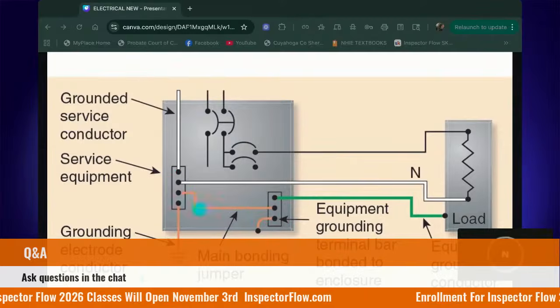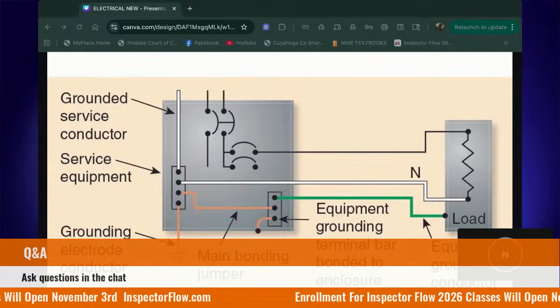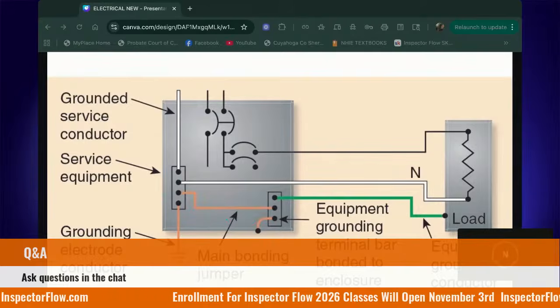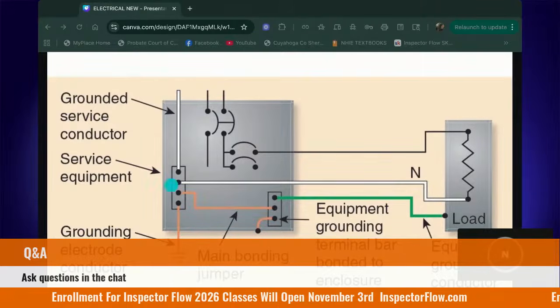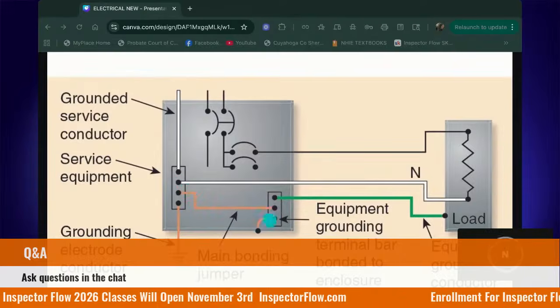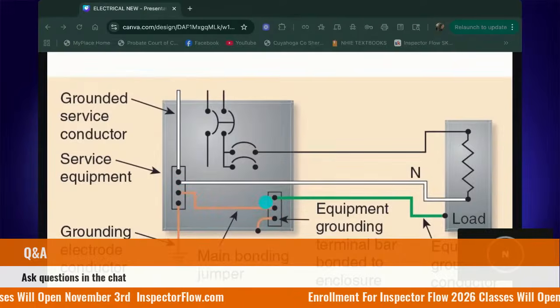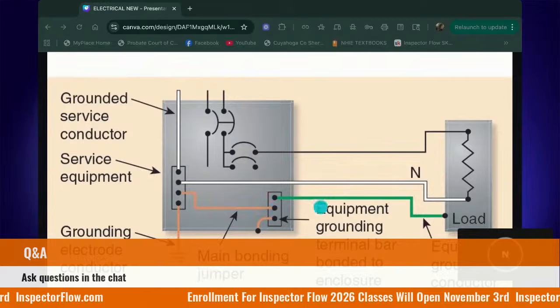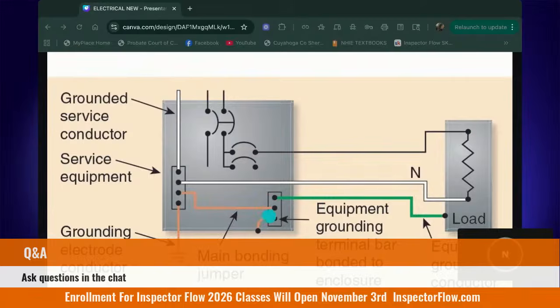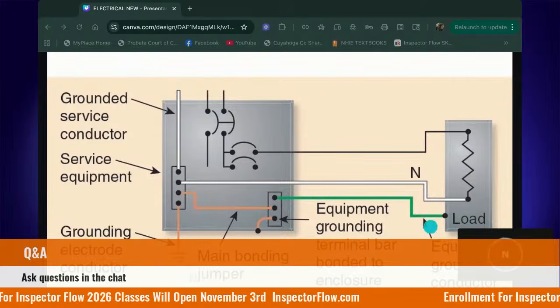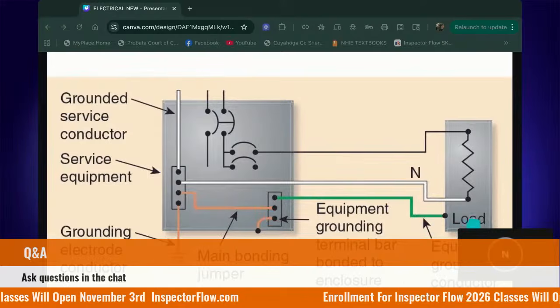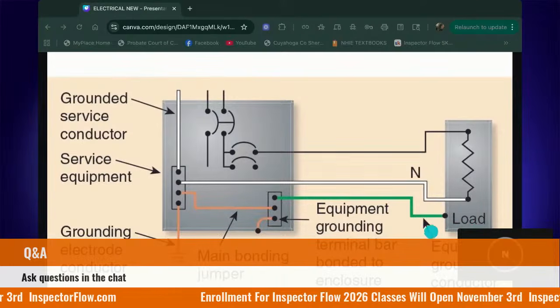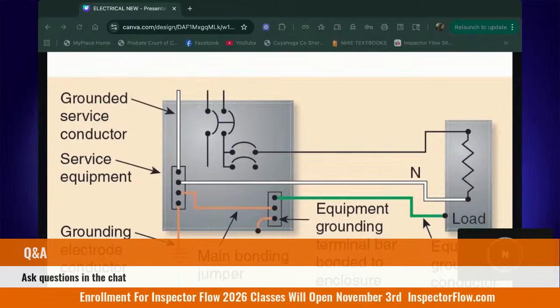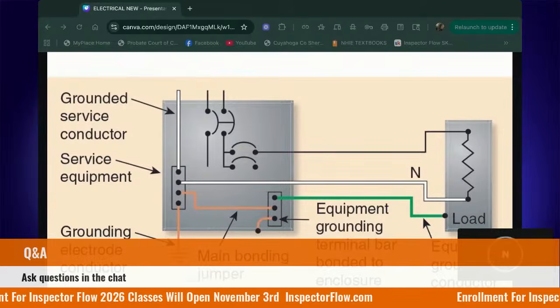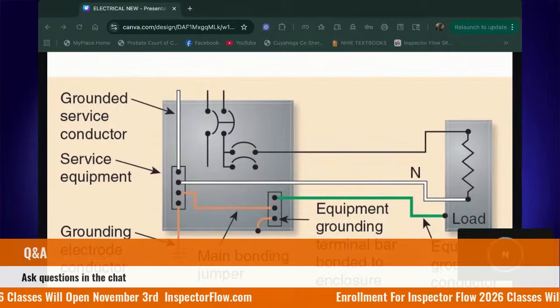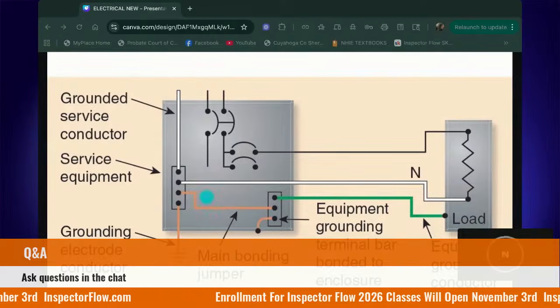It's sort of like we're shaking hands here between the neutral and the ground so they can work together. Then I have my equipment grounding bar, or my grounding bar inside of my panel where my EGCs terminate. So all of my equipment grounding conductors, or EGCs, from my outlets, from my switches and appliances, connect here. They come back to the grounding bus bar. Are these wires carrying current?